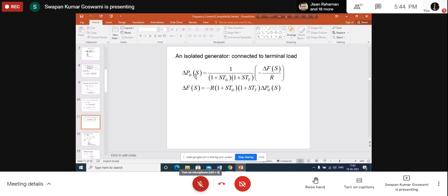So if you connect some load, how much will be the change in frequency or change in speed? If you connect some load, the generator will generate more power. How will it be generating more power? Because there will be a changed steam flow rate. Why will the steam flow rate change? Because of the throttling operation of the governor. It is because of the governor operation only. The governor on its own can do this, and this operation of the governor, when the speed changer position is not changed, is called the free governor operation. That means the governor is free to operate on its own.